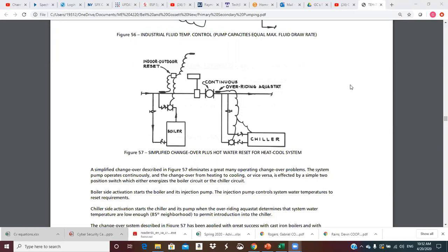The system pump operates continuously, so we're circulating the loop all of the time. The changeover from heating to cooling or vice versa is affected by a simple two-position switch, which either energizes the boiler circuit or the chiller circuit. So we're either going to run the boiler pump and boiler, or the chiller pump and chiller. Boiler side activation starts the boiler and its injection pump. The injection pump controls system water temperatures to reset requirements, with a bulb in the outdoor air resetting the loop temperature with outside air.